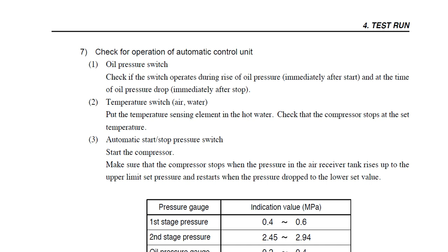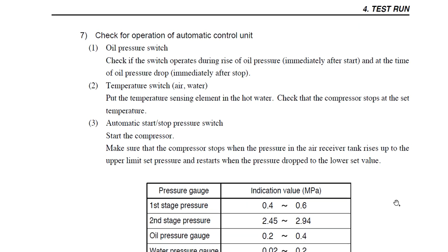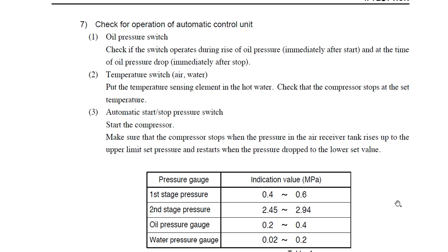Next, we will check also the automatic control that is working perfectly: the switches and the temperature switch, which can be tested with immersing the element in hot water, also the automatic start-stop pressure switch.